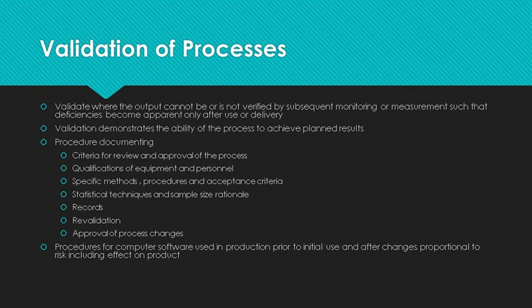If software is used to control production, the software must be validated prior to use and as appropriate after changes. Check with your registrar as to how they view software validation. Many organizations view commercially available software as validated by the software company, some may require all software to be validated, others will require your organization to obtain copies of the software validation from the software companies, and others will accept that if you haven't modified the software, it was validated before sale.